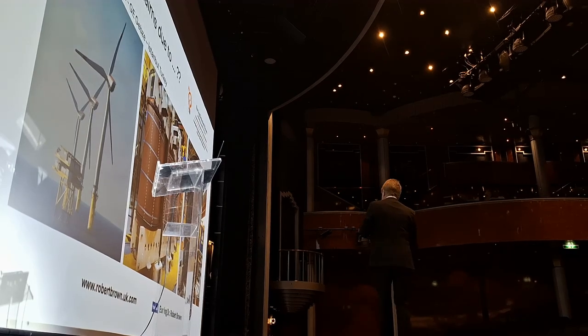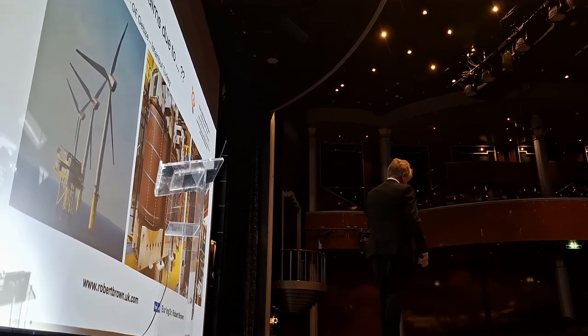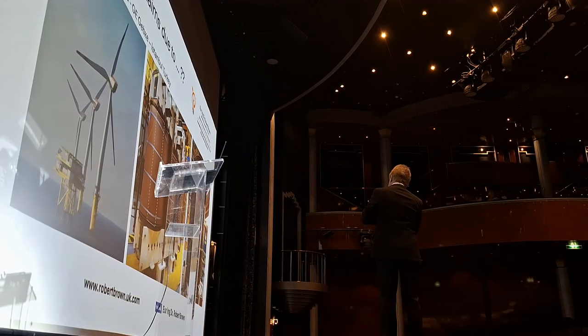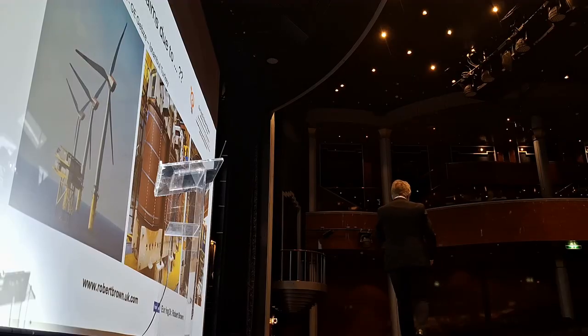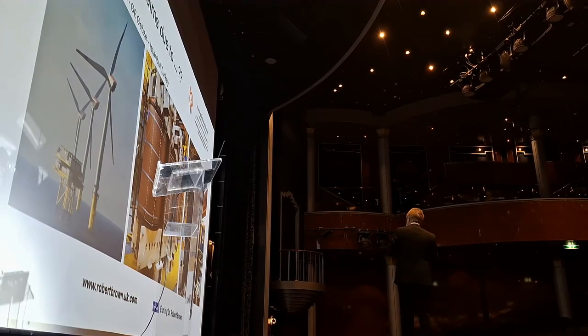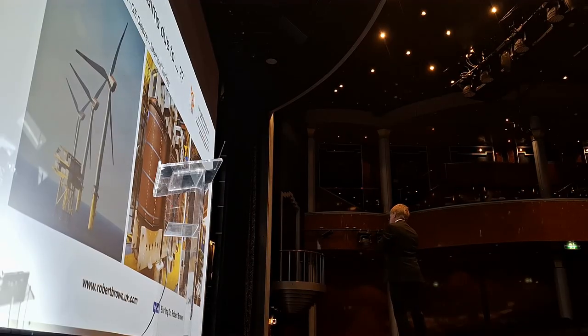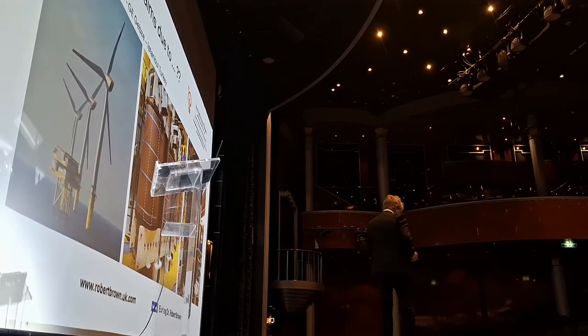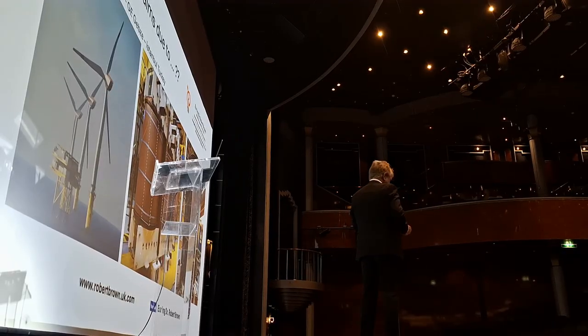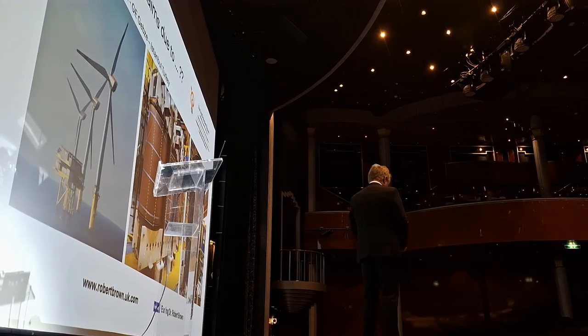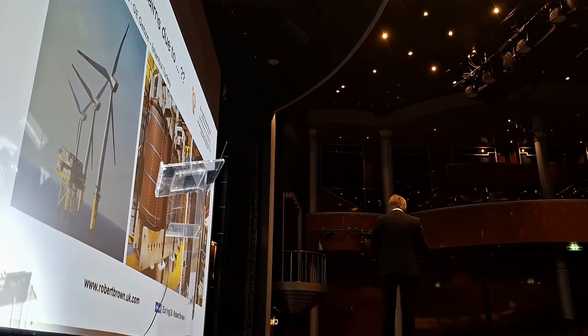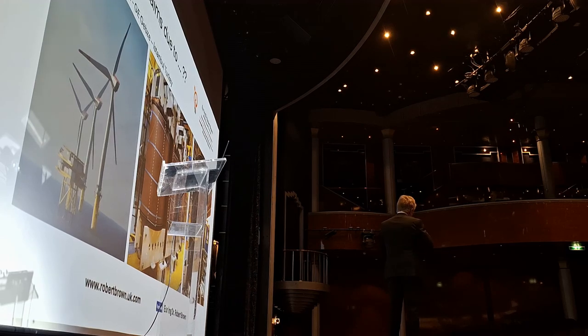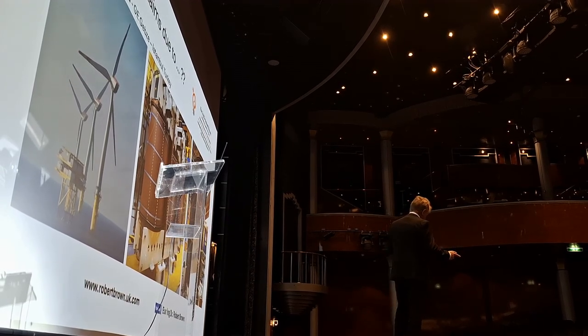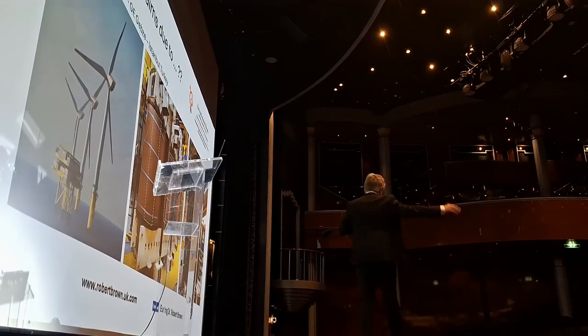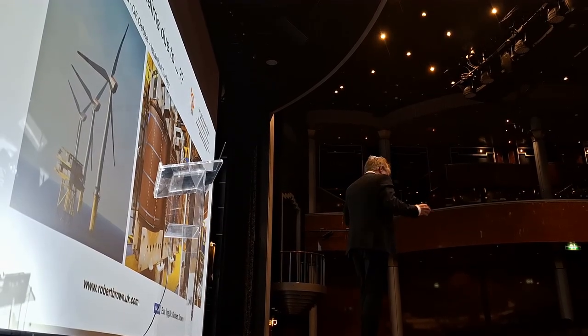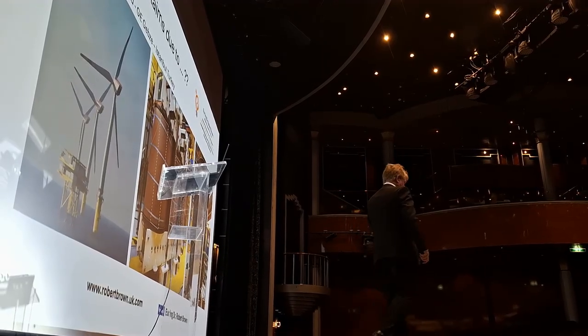And basically this shunt reactor is half a transformer, and it's comprised of these big cylinder things, which are basically copper conductors wrapped in paper for insulation, and all three of them are lowered into a tank, and the tank is filled with oil, a special mineral oil. The reason it's mineral oil is that the electrical withstand capabilities of oil are greater than air. We could build this thing and separate them by air, but it'd be massive. So to reduce it in size, we dunk it in a vat of oil.